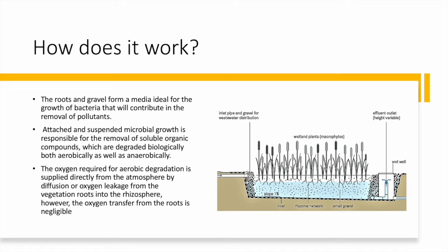The inlet pipe disperses water into the wetland at the top of the inlet section, covered by coarse gravel. The treatment process occurs within the root and gravel area, which forms an ideal media for bacterial growth. These bacteria eat the organic matter and pollutants in the wastewater, with both attached and suspended microbial growth responsible for removing soluble organic compounds.